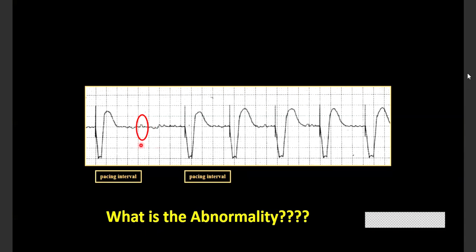Oversensing should be suspected when you have bradycardia or when the pacemaker is not firing when it's supposed to fire. So here you're expecting a pacemaker firing. When it's not firing when it's supposed to fire, you think that one reason could be that the battery is depleted, or the other reason is it is oversensing something. And common causes for oversensing would be atrial events, myopotentials, or external impulses. Okay.